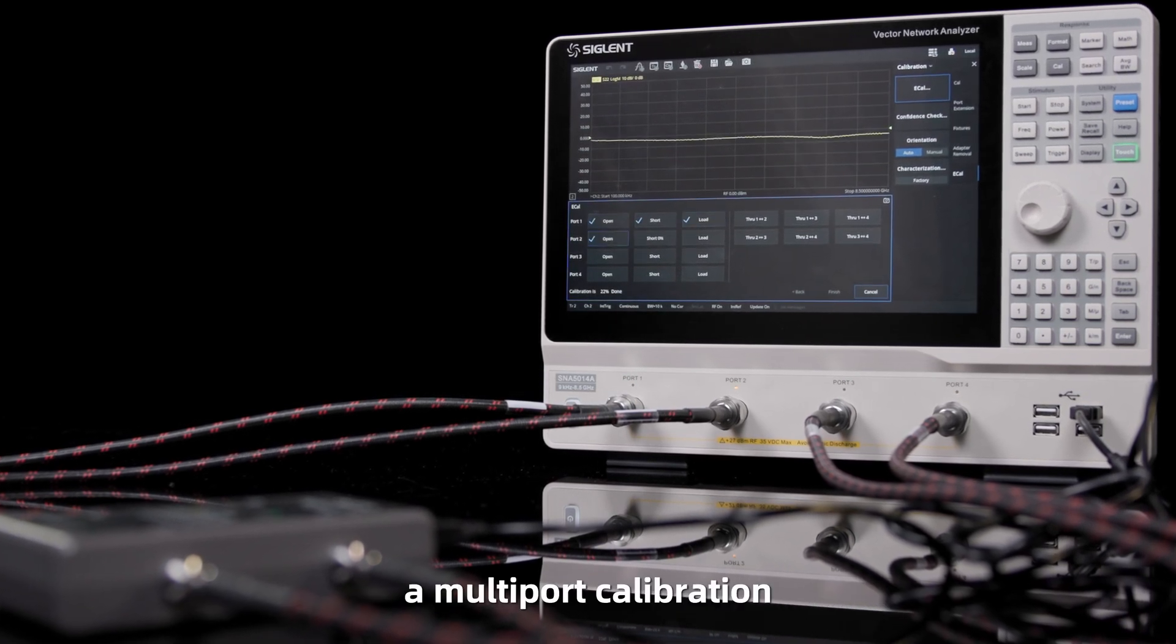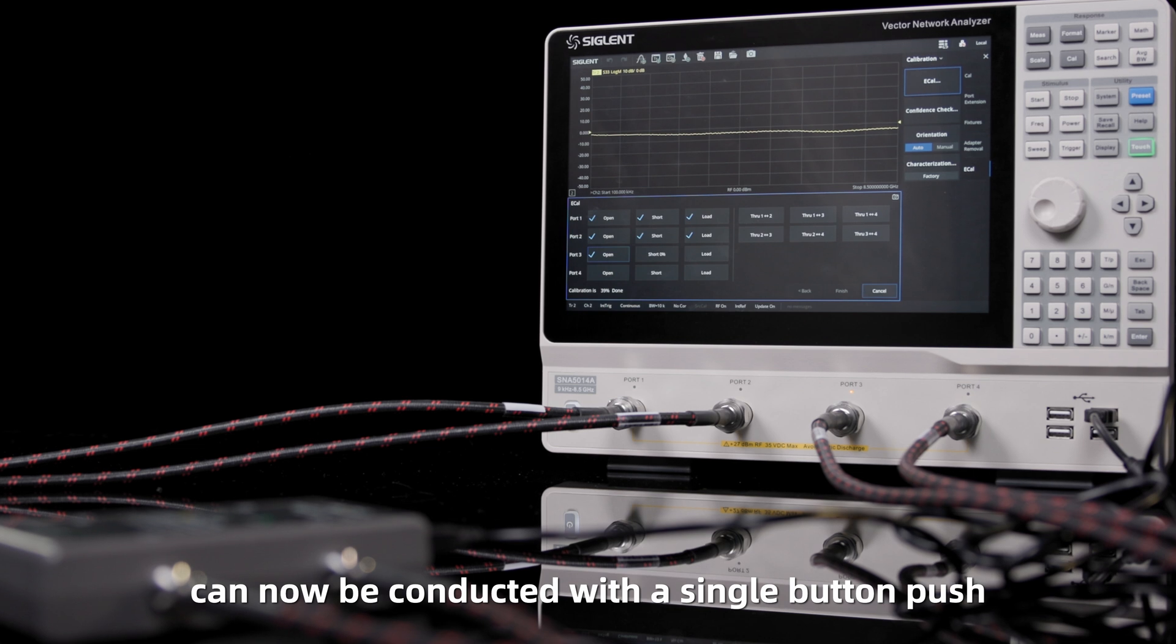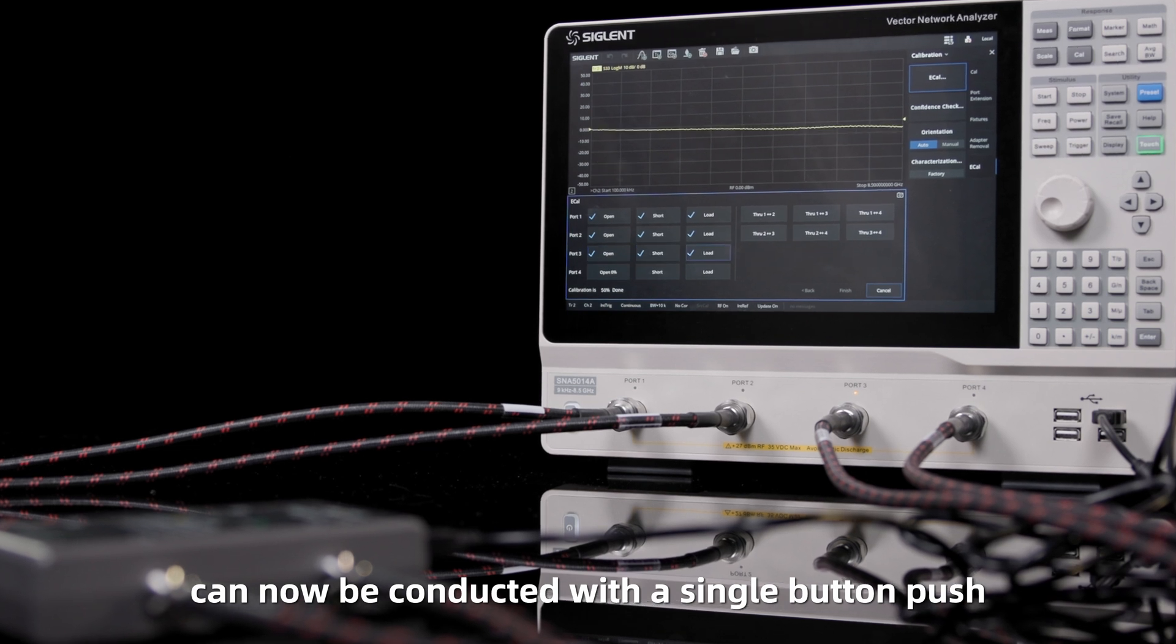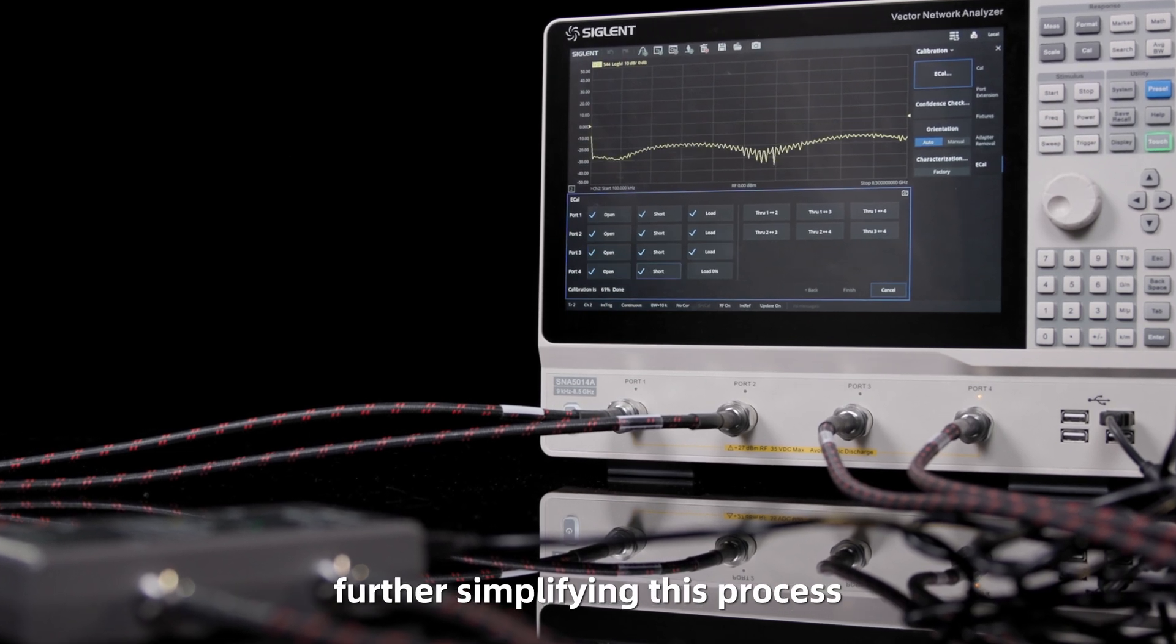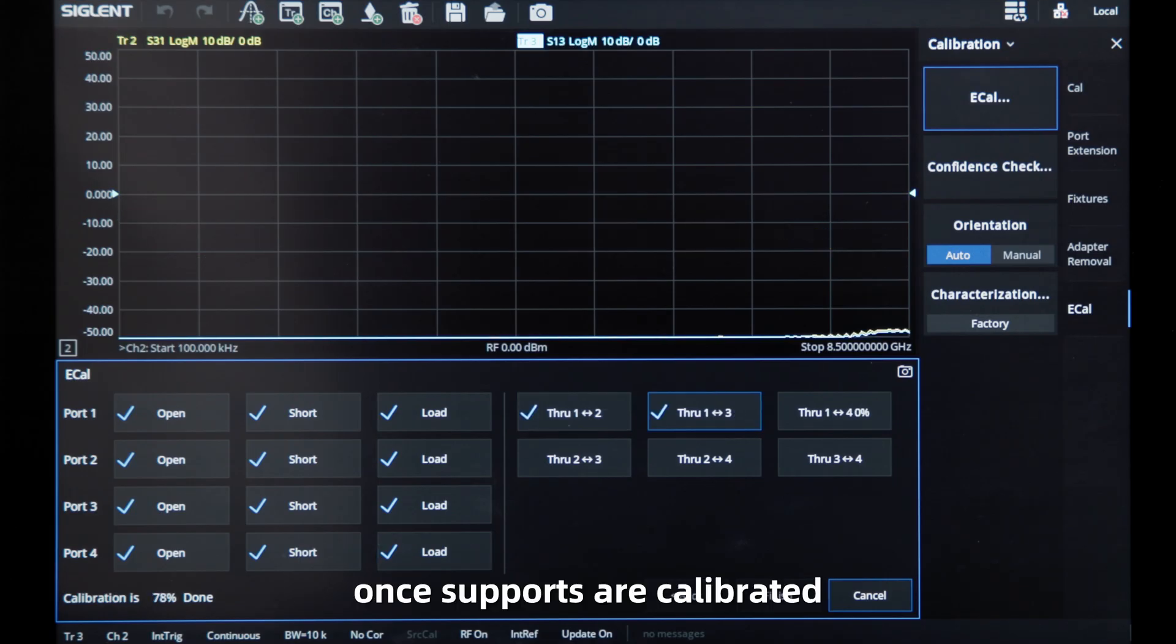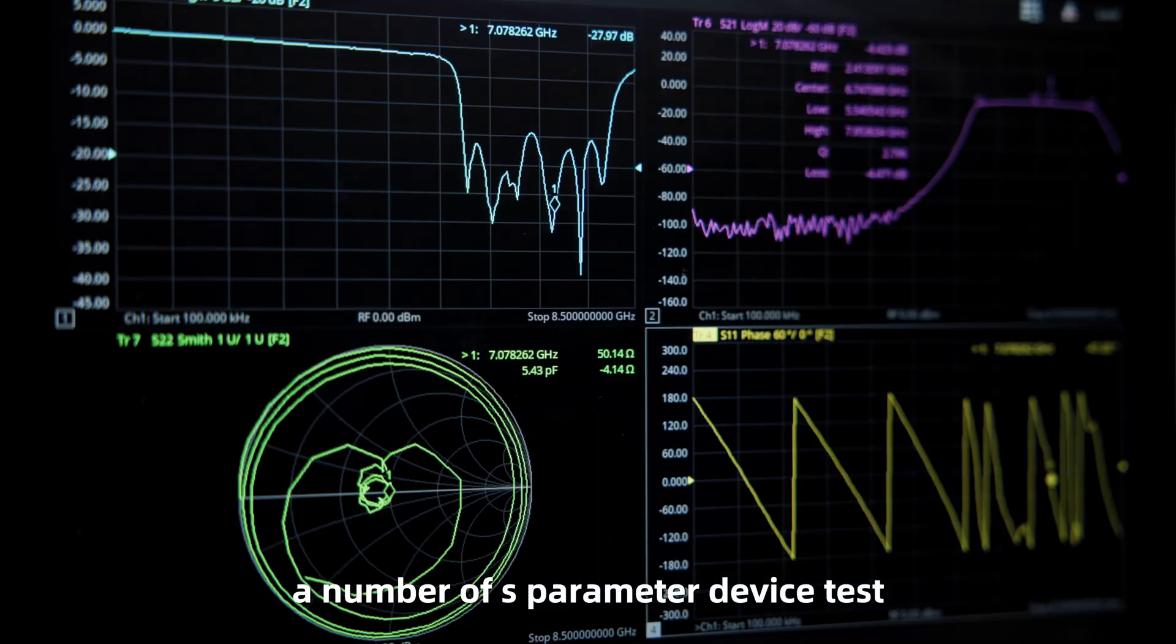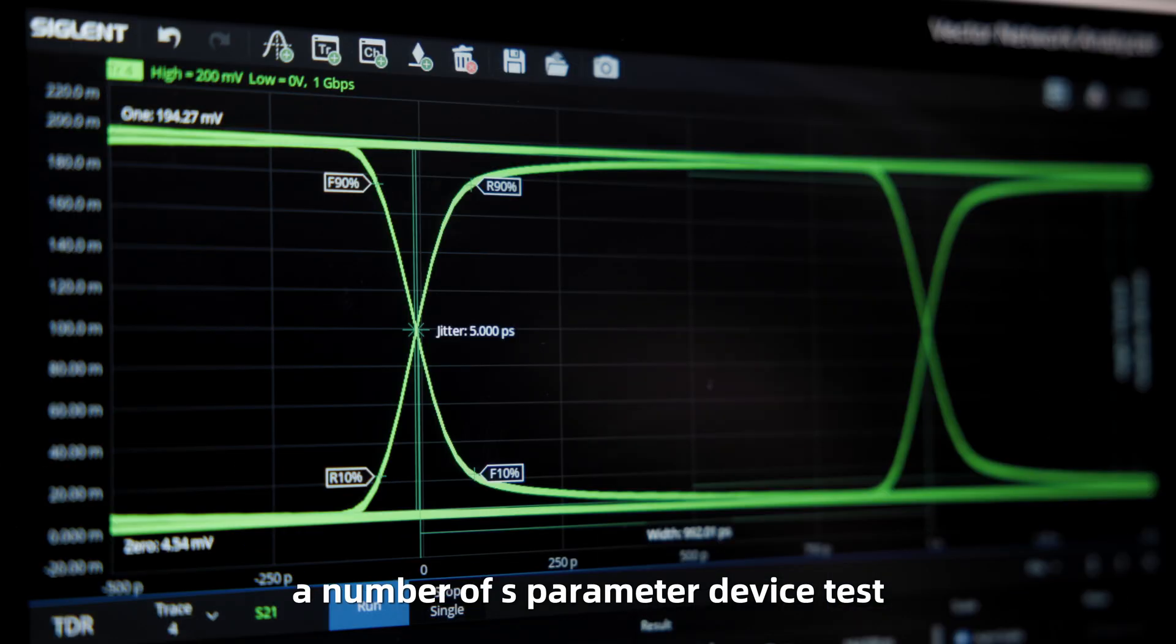A multi-port calibration can now be conducted with a single button push, further simplifying this process. Once the ports are calibrated, a number of S-parameter, device tests, and TDR measurements are possible.